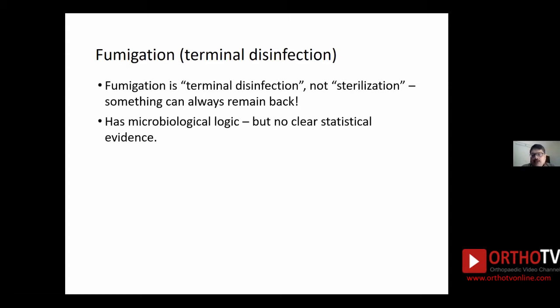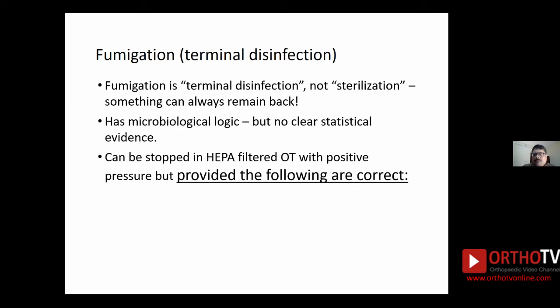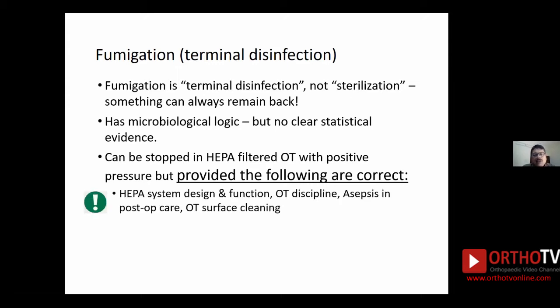Fumigation methods have microbiological rationale but no clear statistical evidence that they directly reduce surgical site infections. For HEPA-filtered OTs with positive pressure, fumigation procedures can be stopped provided four things are correct: the HEPA filter system design and function is perfect; OT discipline is followed by everyone including surgeon, anesthetist, and staff; asepsis during post-op care is properly assured and monitored; and OT surface cleaning is as best as possible. In the Indian scenario, these four conditions may not be correct in most hospitals.